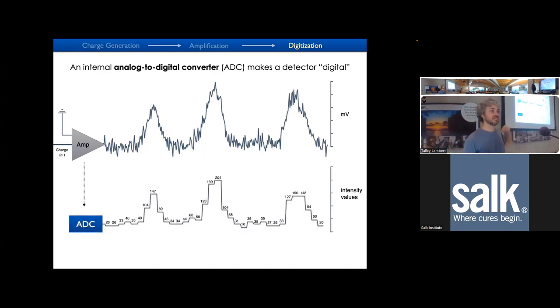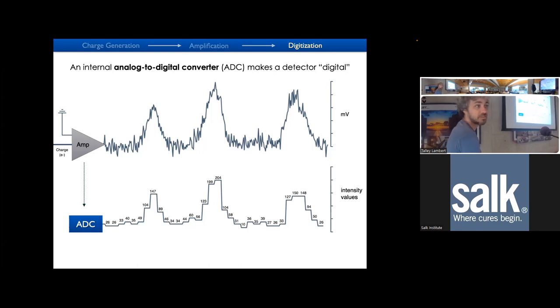Up till this point, we've been dealing with electrons and voltages. Now is the step where we convert our voltage to gray values. This happens at an analog-to-digital converter - a device that takes in voltage and spits out a discrete number. What comes in is a continuous value of voltage, and what comes out is integer values discretized into intensity values. We'll never see a decimal value like 100.5 or negative values.